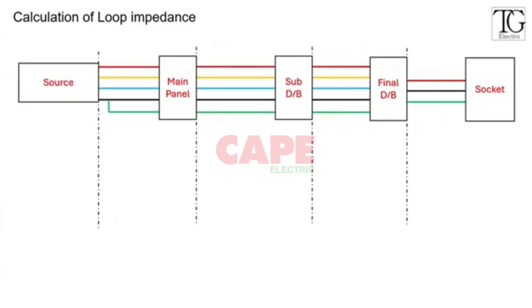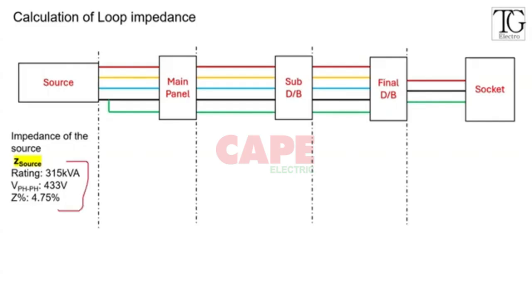Now I'll take a model, with ratings and all those things, so I can explain how you make those calculations. First, the impedance of the source. I'm taking a model rating of 315 kVA rated power, the line-to-line voltage is 433 volt, and the Z percentage is 4.75 percent.